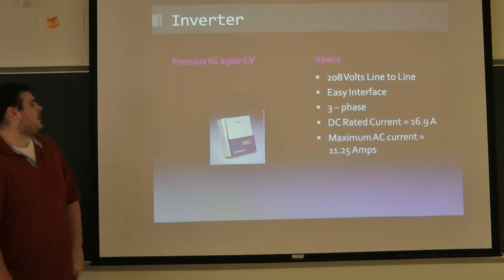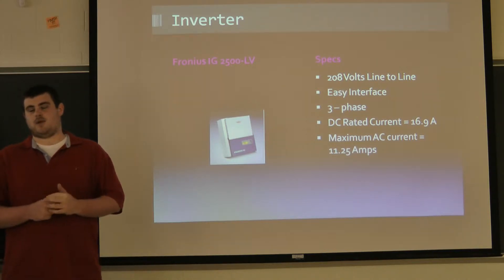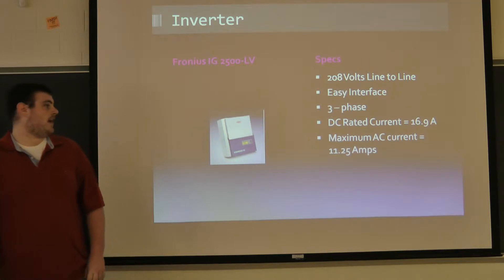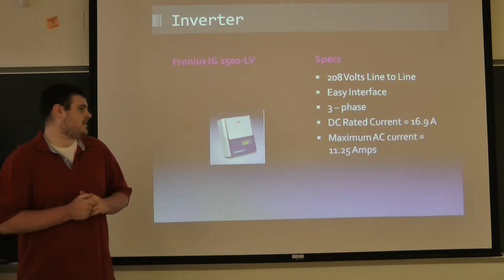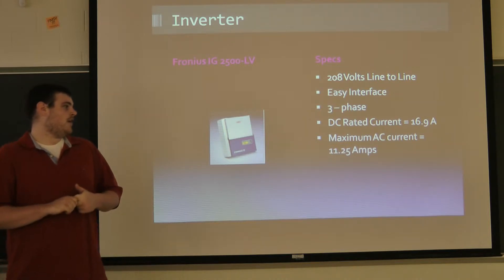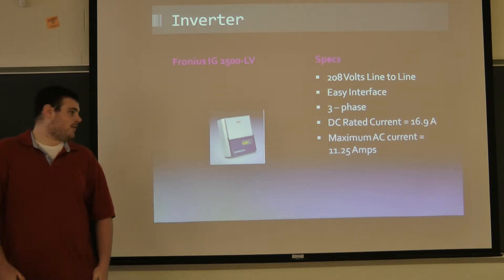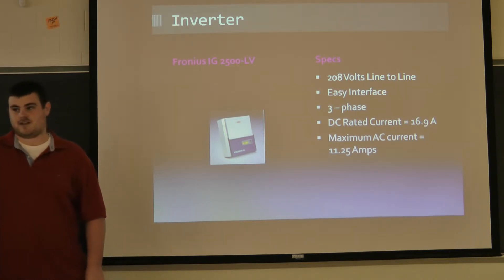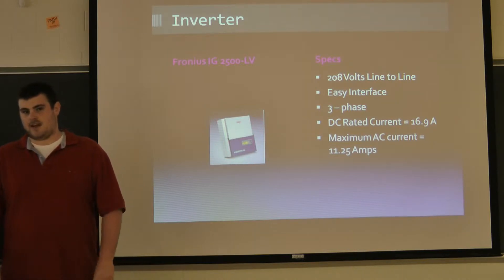The specific inverter we are going to use is called a Fronius IG 2500-LV. For our design, we needed 208 volts line-to-line and three phase. This specific one has a DC rated current of 16.9 amps. Our design is going to be a little more than that. It also has a very easy interface to transfer data into the computer.